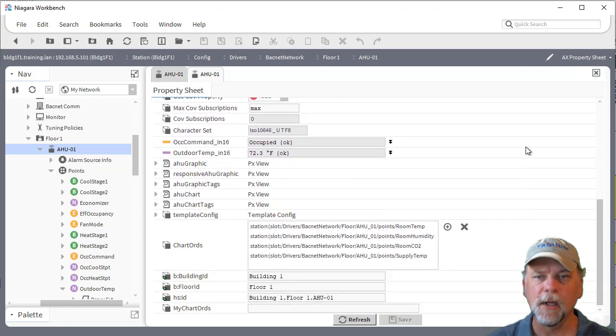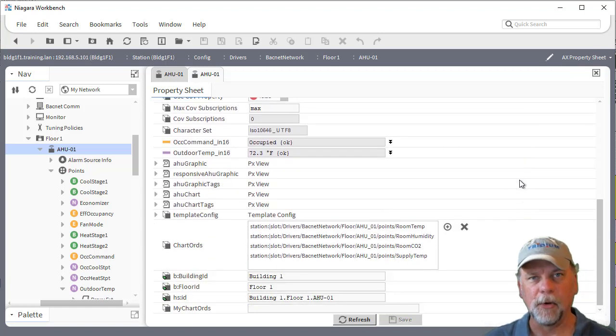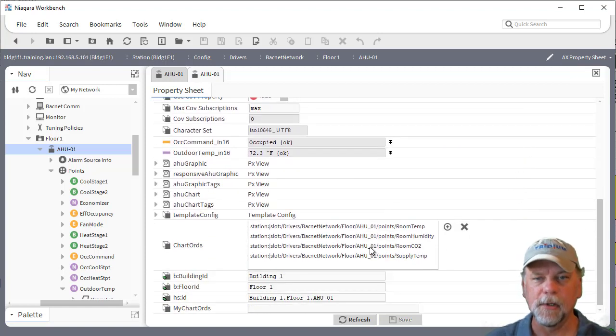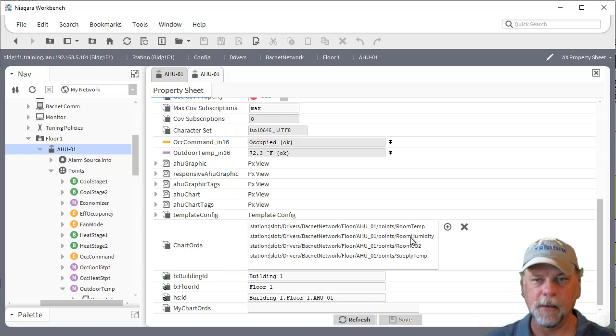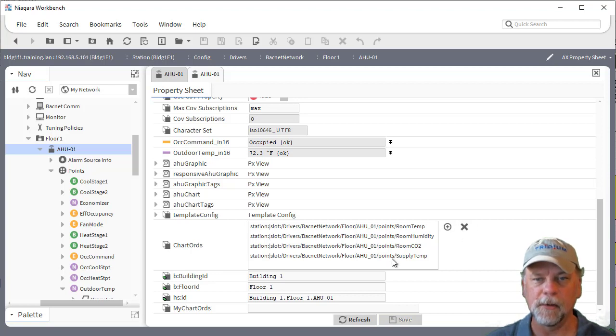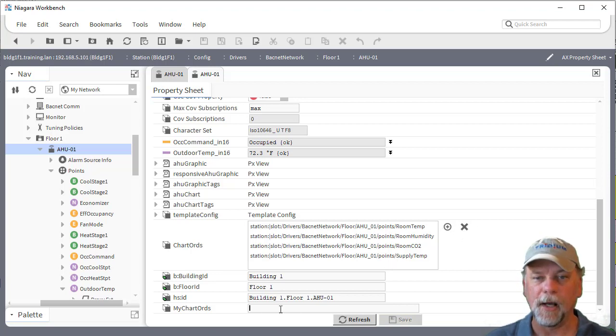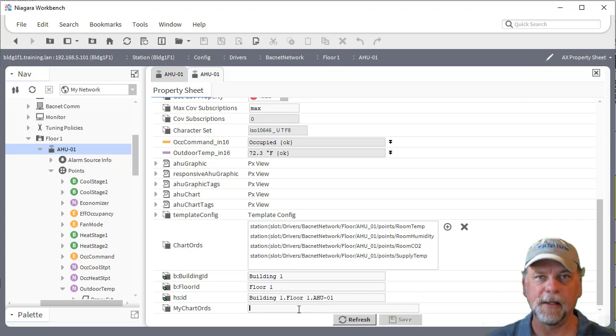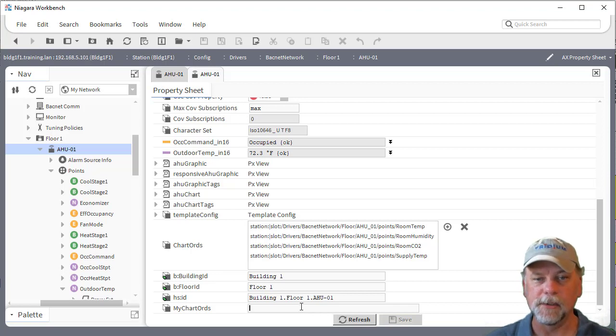When you add the multi-line facet and set it to true that's going to make the field editor be a multi-line field editor with the plus and x icons here for adding and deleting ORDs from the field editor. Otherwise you just get a single line here which is kind of difficult to enter multiple ORDs into or at least to see them.